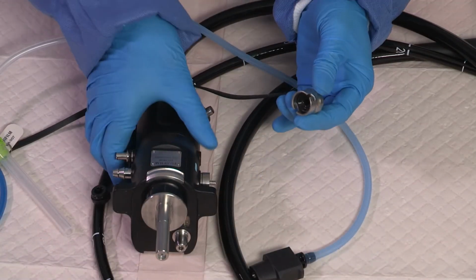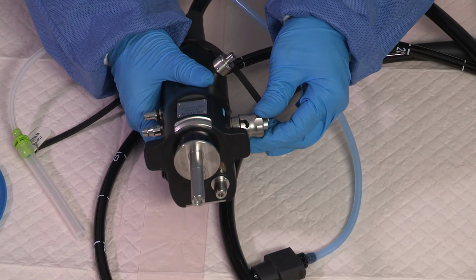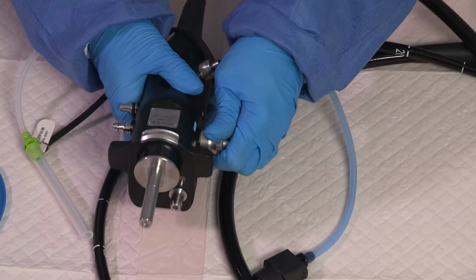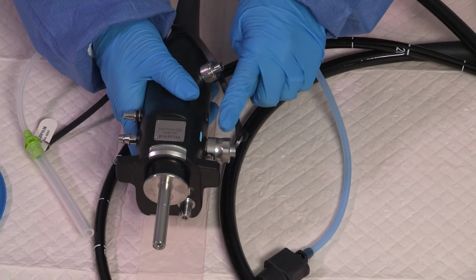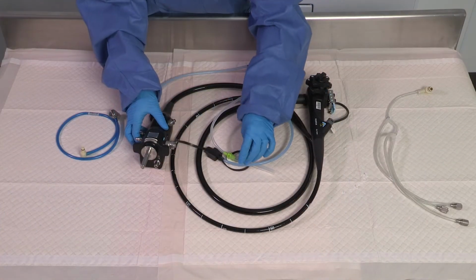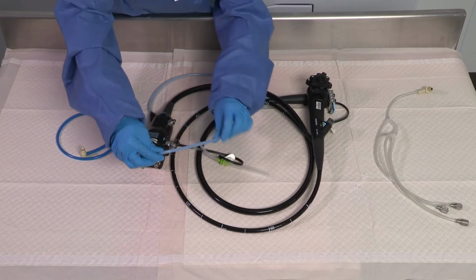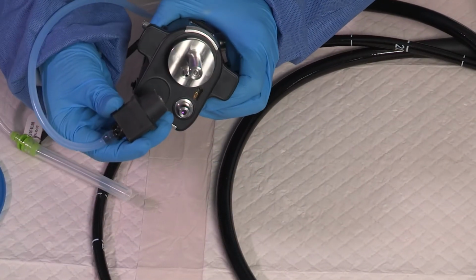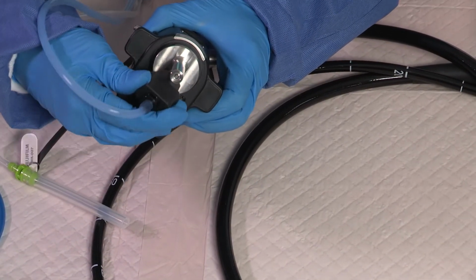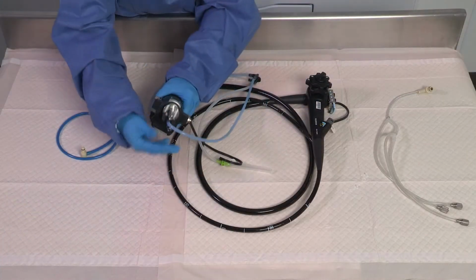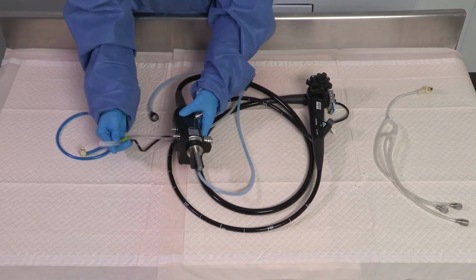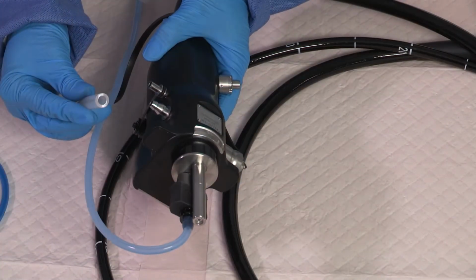To attach the Fujifilm injection tube to the endoscope, align the pin of the water supply connector of the endoscope with the notch of the tank receiving cap. Push the cap and rotate clockwise until it stops to secure it. Attach the air pipe port of the injection tube to the air guide port of the endoscope until it stops. Push the suction tube on the endoscope suction connector until it stops.